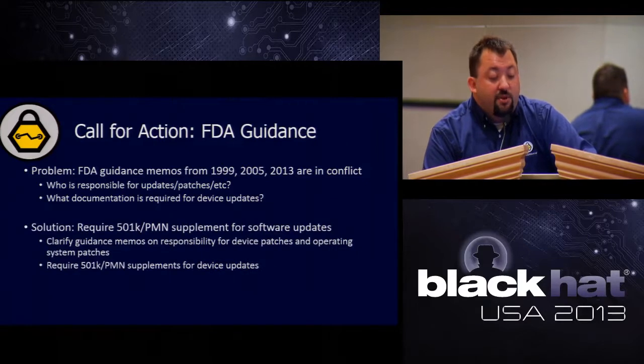My recommendation is to require a 501k or a PMN — those are the two ways you can get a medical device approved — to have a supplement for software updates. I went looking through these; they're all publicly available through the FDA's websites. There are some manufacturers, when they update their software, they have a little note attached to it. It's just a supplement that says, hey, we updated this, and it doesn't even have to have a super detailed description — we updated this because we found some bugs and we fixed it.